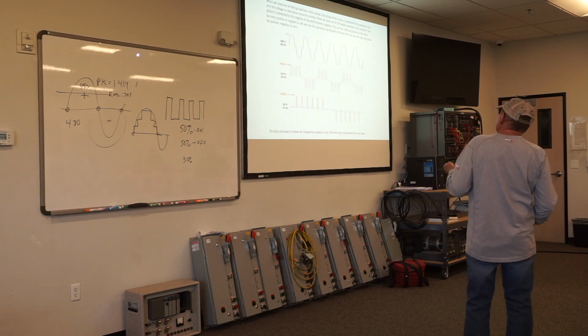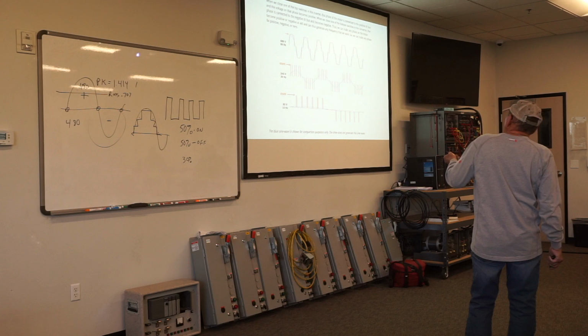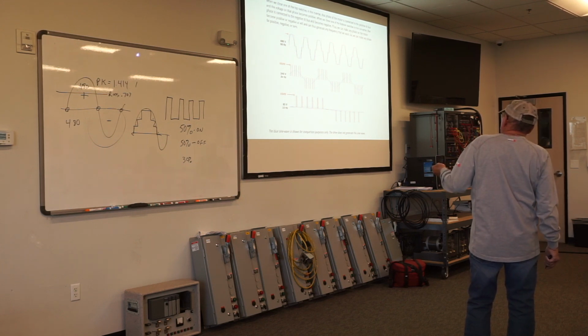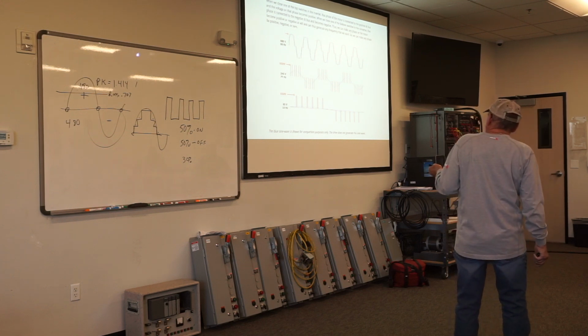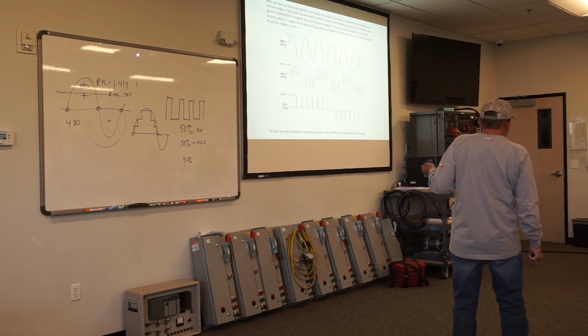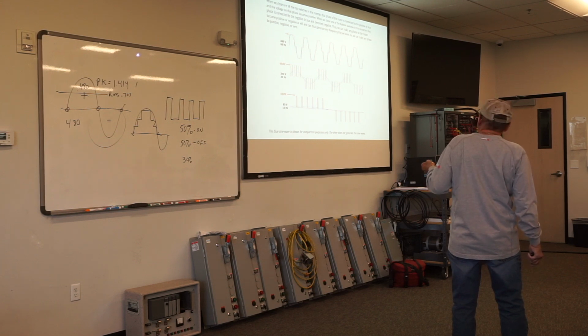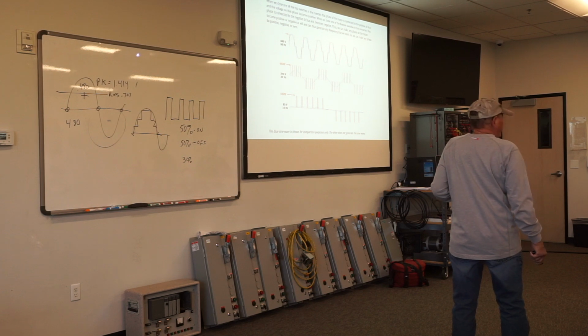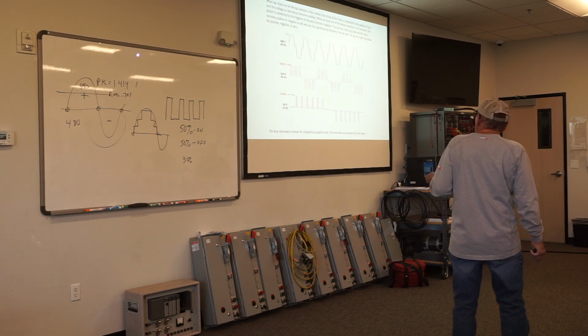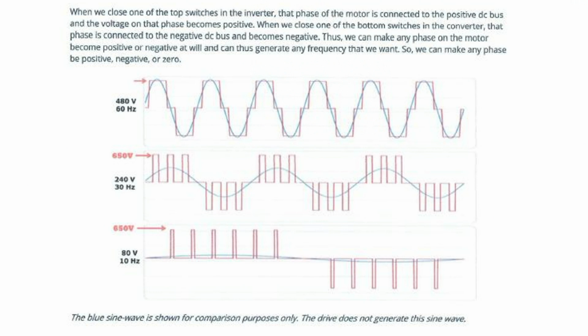So basically, in order to slow the motor down, we slow the frequency, but in the process, we have to lower the voltage. So as I go from 60 hertz to 30 hertz, I start out at 480, therefore my frequency drops in half, my voltage drops in half. But my DC bus is still 650 volts. Now if I drop to 10 hertz, so I'm 1/3 of 30, my voltage is 1/3 of 240. So it's all pretty linear.